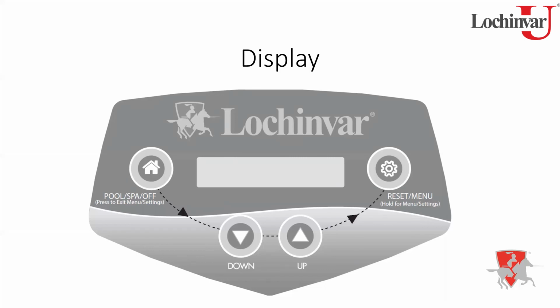So when you first power it up, the display will be in what's called a lock condition. To unlock it, to be able to use the buttons or to get into the parameters, you do have to basically do what's called a finger swipe, going from the pool spa, working from left to right, down through your up, into the reset menu. So you're just going to swipe your finger along that path, and that will unlock the display to allow you to make changes. Now, there is another layer of protection. We can actually activate a passcode feature that would require you to put in a passcode if you wanted to get in to play with it. We can do that, and we'll show you how to do that in just a second.